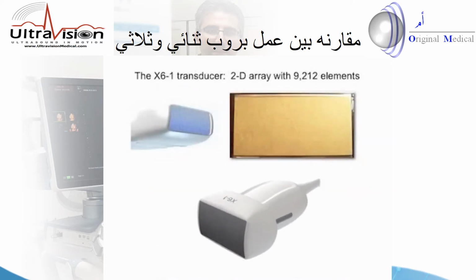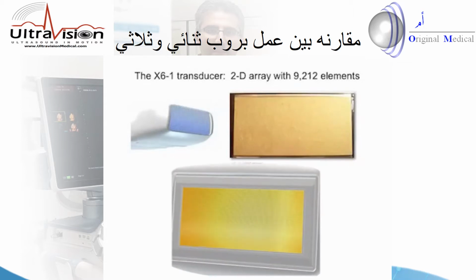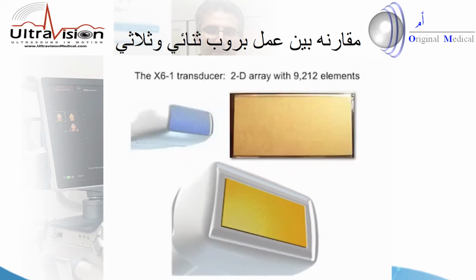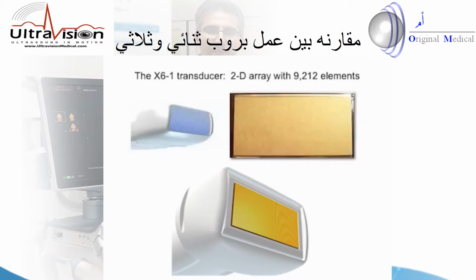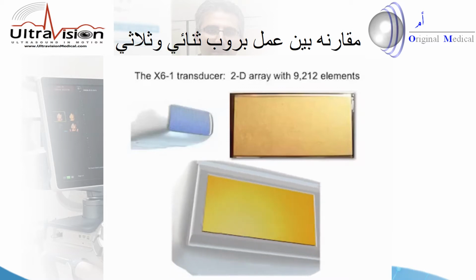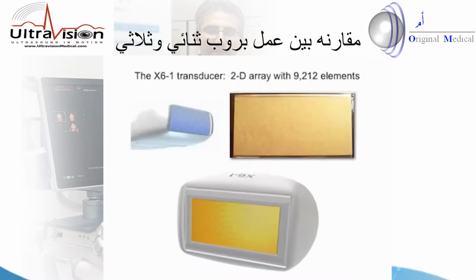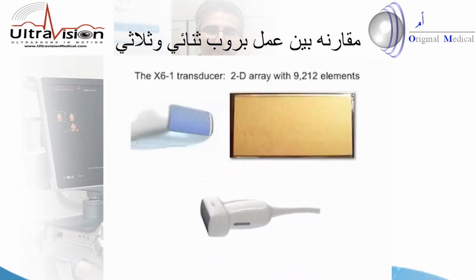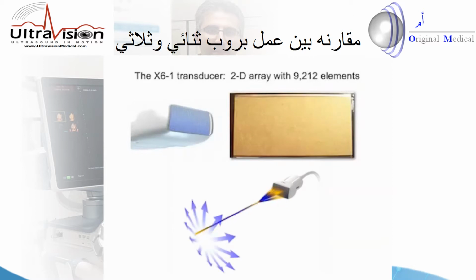The X6-1 is quite different. It doesn't have a line of elements, it has a two-dimensional array of elements. And although the area of the footprint of the transducer is comparable to that of a conventional abdominal transducer, there are a great deal more elements there, not 100 or 200, but 9,000 elements in the case of the X61. And I think you can see immediately that such a transducer, if one had control of all of those elements, could be used in many different modes.